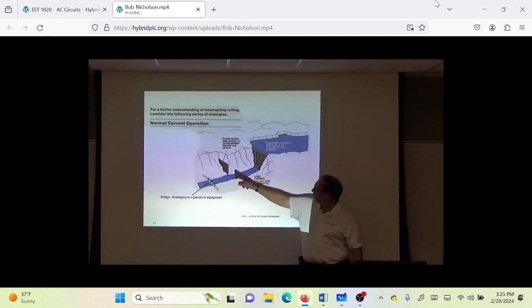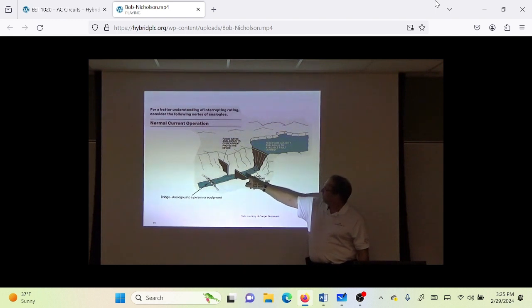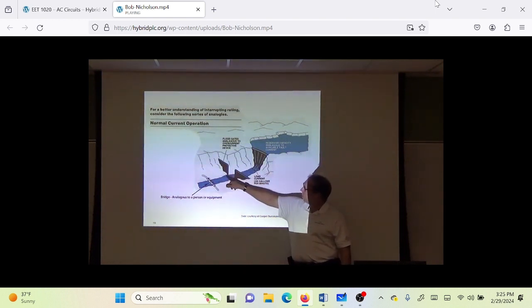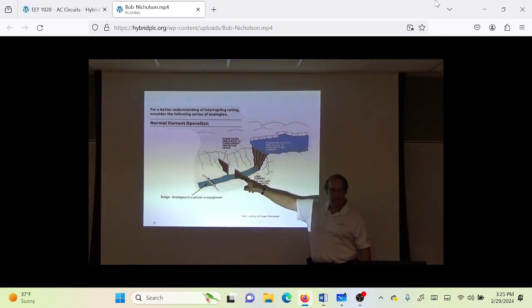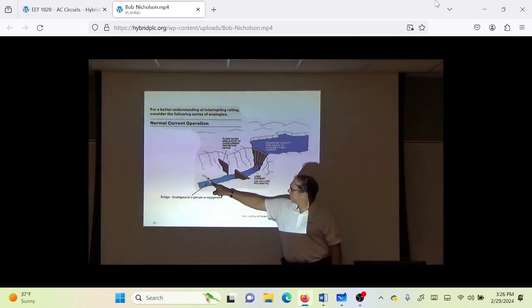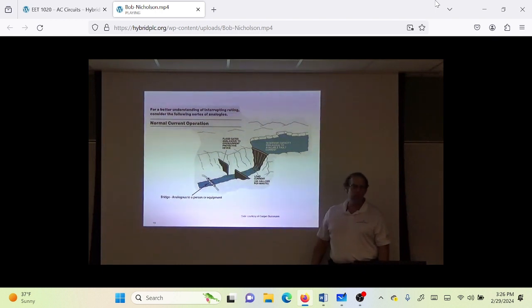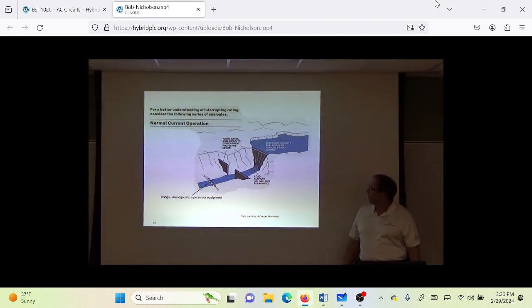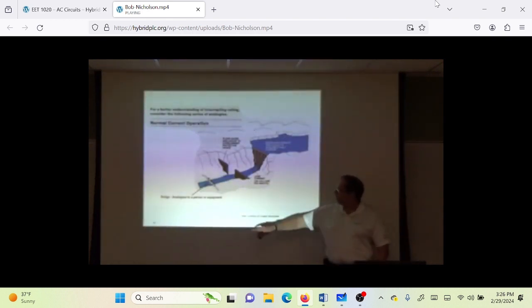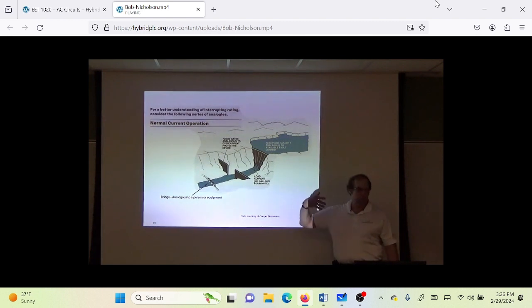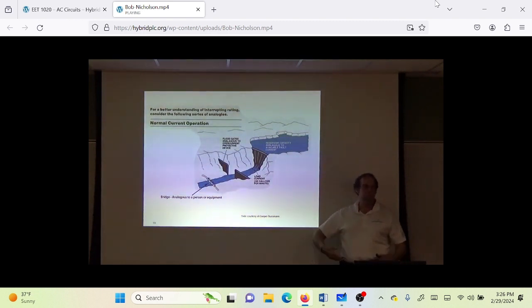That 400 amps is going to go to a sub-panel. This is the sub-panel. That is one breaker inside of the sub-panel now, that gate. So we're going to call that 100 amps. It's going to go down a wire, and it's going to go to a panel where somebody is working, and we're going to call it the bridge. Okay? So right now, the only hazard that there is electrocution. If you touch something right there, you're going to be electrocuted. There is no arc flash because there's no fault. The fault has to occur here. Either a person creates it or equipment creates it. Something has to create it.